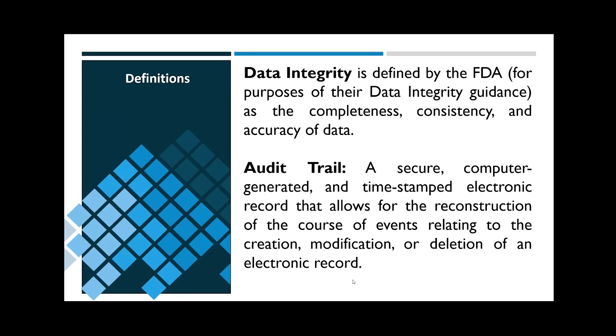We'll dive into an overview in a moment, but first I want to define a few more relevant terms. The first one is audit trail. An audit trail is a secure, computer-generated, time-stamped electronic record that allows for the reconstruction of the course of events relating to the creation, modification, or deletion of an electronic record. If I look at an audit trail, I should know who specifically performed the action that generated the record, what the record is — for example, a setpoint change from 37 to 36 degrees Celsius — when the record was generated, and what unit op, say a single-use bioreactor, the change occurred on. Many systems allow for the operator to leave a comment explaining the change, and that's our why.